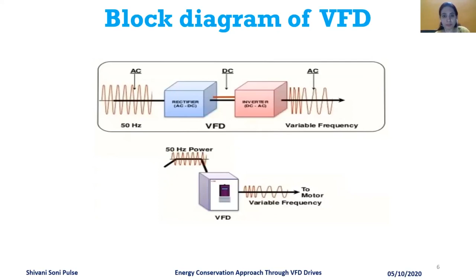So let's see an example of how the VFD's role affects the power consumption in industry. There is a flow application where they are using pumps of 15 HP or 10 HP as provided. If we are not using the VFD, then we see a number of losses, as generally a mechanical throttling valve is used for pump applications, so there are a number of losses we can calculate here.